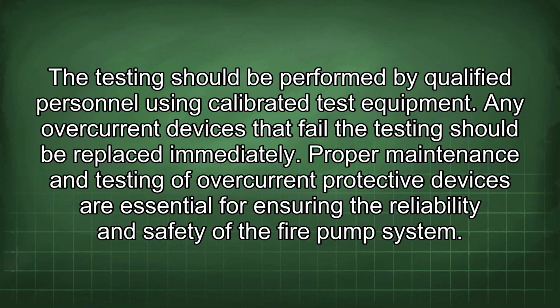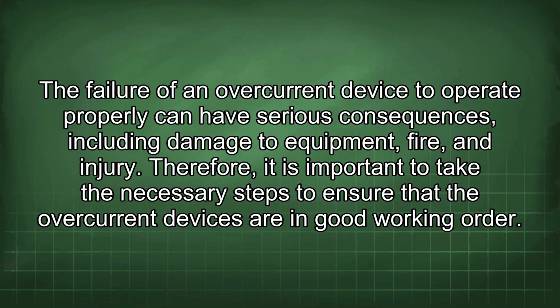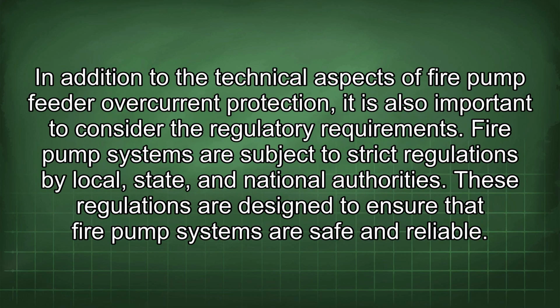Proper maintenance and testing of overcurrent protective devices are essential for ensuring the reliability and safety of the fire pump system. The failure of an overcurrent device to operate properly can have serious consequences, including damage to equipment, fire, and injury. Therefore, it is important to take the necessary steps to ensure that the overcurrent devices are in good working order. In addition to the technical aspects of fire pump feeder overcurrent protection, it is also important to consider the regulatory requirements.